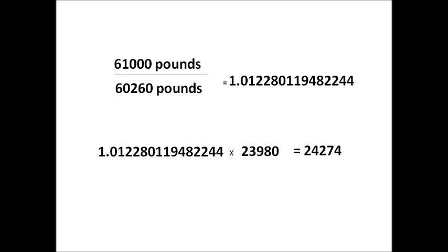So, for example, we take 61,000 pounds of known weight, divide it by what the indicator said of 60,260 pounds, which equals our new calibration factor. We take that times 23,980, which will then equal our new calibration number of 24,274.